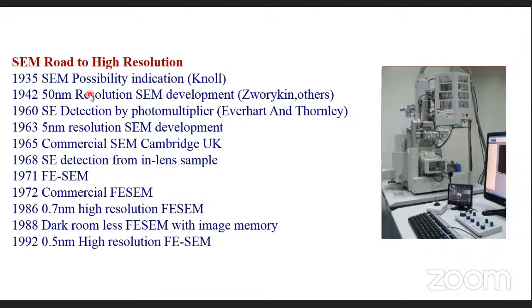Whenever you need high clarity and high resolution images, you should go with the field emission scanning electron microscope. The difference between these two is exactly like the production of electrons — in thermionic emission, an ordinary tungsten filament is used, but in FESEMs they use a Schottky field emission tip for better production of electrons and better image resolution.